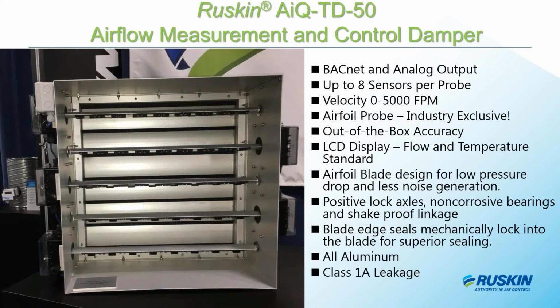This is a photo of what we were showing at the ASHRAE show this year. It's, again, air measurement in a sleeve with a control damper. We have all the features of the TDP05K plus the features of the CD50 control damper in this sleeve available with or without an actuator. In this configuration, the automation system reads the air measurement from the TDP05K and then controls the damper actuator to maintain the desired airflow. This is called controls by others. Any brand actuator can be included as an option and supplied by Ruskin, factory mounted prior to shipment.